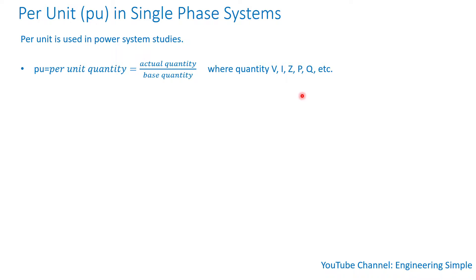It can also be reactive power in megavars or kilovars. The base quantity is picked conveniently for the study. For MVA, industry-wide, 100 MVA is commonly used as the base, and then all quantities are converted on that base. For example, if your generator or transformer is rated 700 MVA, then 700 divided by 100 equals 7 per unit. You do the same for voltage — pick a base voltage and convert all voltages to that base.